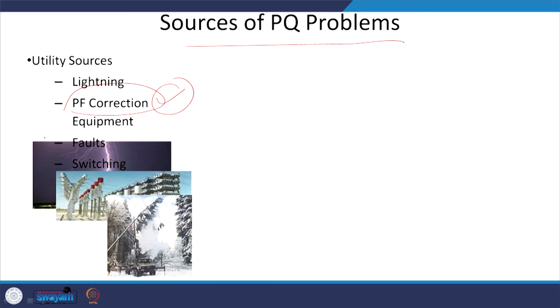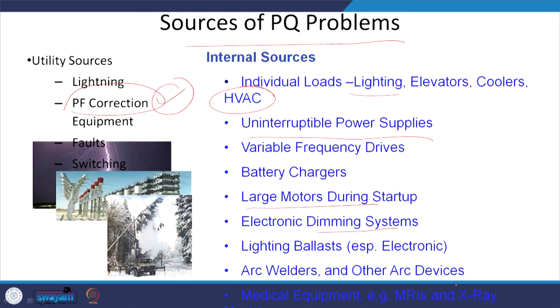You see the placing of the capacitor for correction of the power factor, and what is its effect on the overall power quality. So, these are a few issues, that is individual, and it can be internal sources, that is individual loads, that is lighting. Nowadays, we have LED lights. So, elevators, coolers, HVAC, thereafter uninterruptible power supply, variable frequency drives, battery chargers, large motors during start, electronic dimming systems, lighting electronic ballasts, arc furnaces, medical equipment, MRI, etc. So, these are a few categorized as problems.